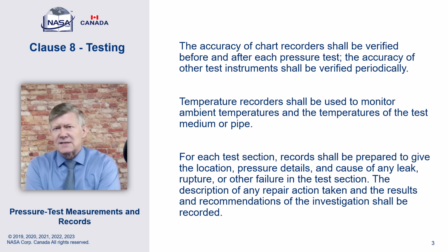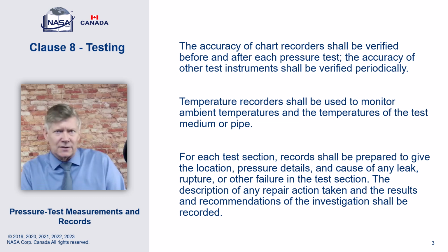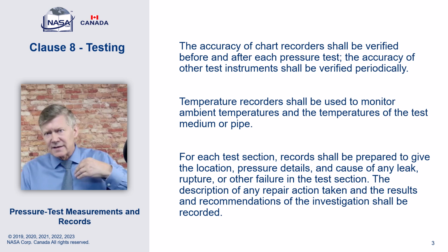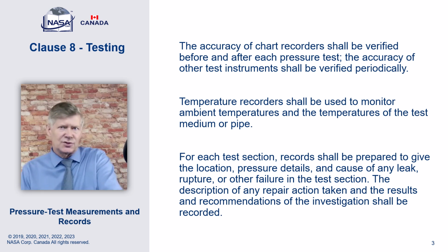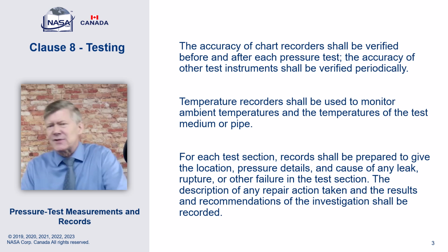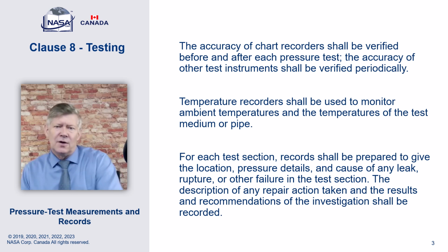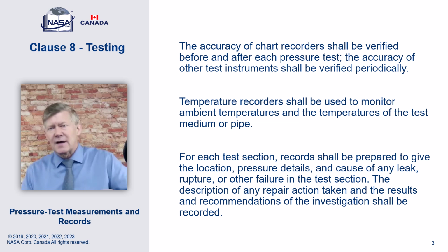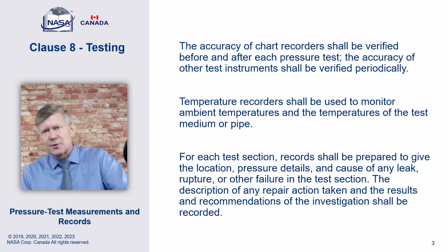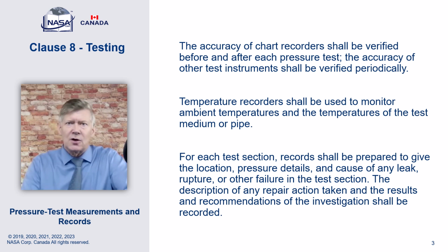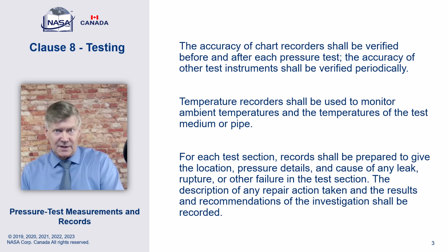So Z662 looked at it and said, no, the calibration thing doesn't really work. Not for us in this circumstance, okay? Because what we've got is a history or an understanding in other jurisdictions, other countries, where they have the calibration requirement. When instruments come back out of calibration, people don't redo the test. They just say, it's probably close enough, right? And so we really didn't want to have that. And this is a second-party system, right? The company bears full responsibility.